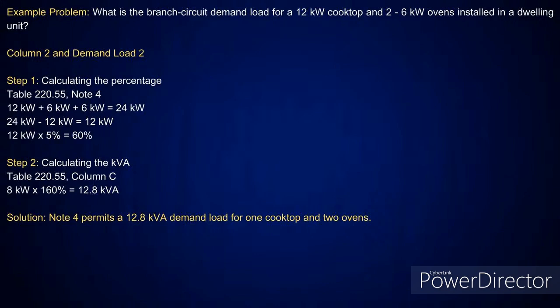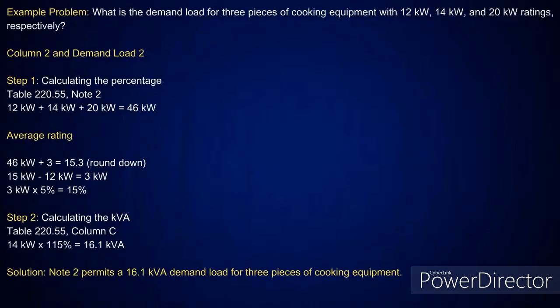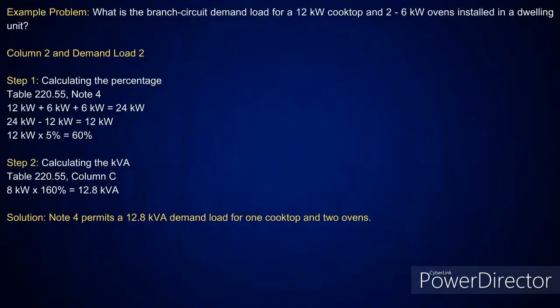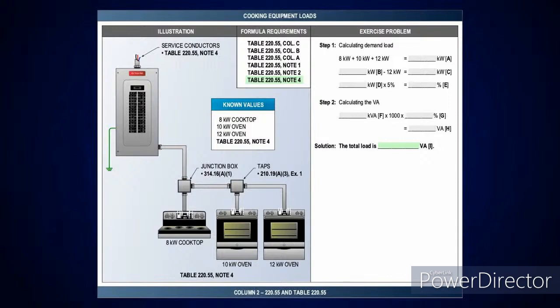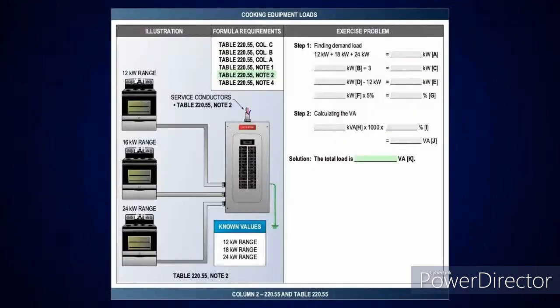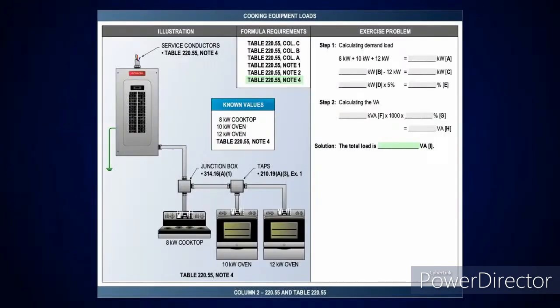Now, when you're taking the test, if they tell you what is the branch circuit demand load, may put something like this, you know it's on one circuit. It's not on 3 individual like I was doing back here. Right. See, I've got 3 individual pieces of cooking equipment. Here, we're telling you it's on a branch circuit. And then if you look at the illustration, look at that illustration and look at this one. Right. 3 individuals. This one here is on one circuit. Yep. See that?